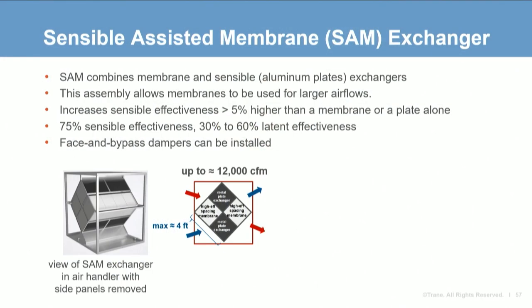The next type is the sensible assisted membrane, or SAM. SAM is a cross-flow heat exchanger that combines membrane exchangers and sensible aluminum plate exchangers together in one assembly. This expands the scale where membrane exchangers can be used, increasing the airflow range where total energy recovery cross-flow exchangers can be used, allowing them to be applied in larger commercial buildings. The smaller size SAM allows the use of high-efficiency membrane spacing exchangers.